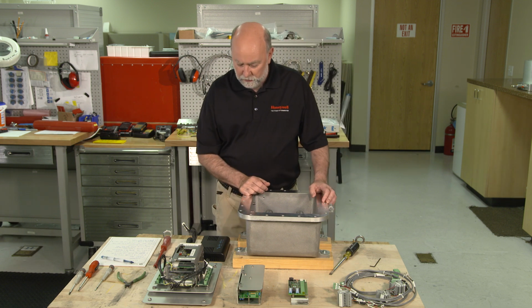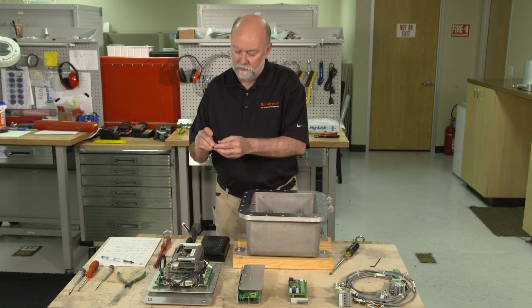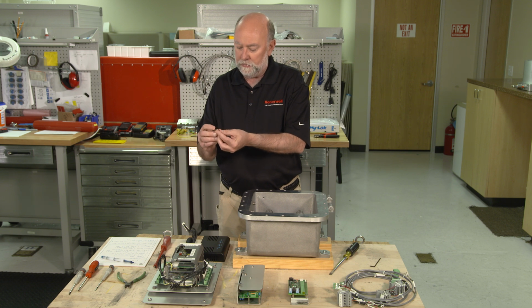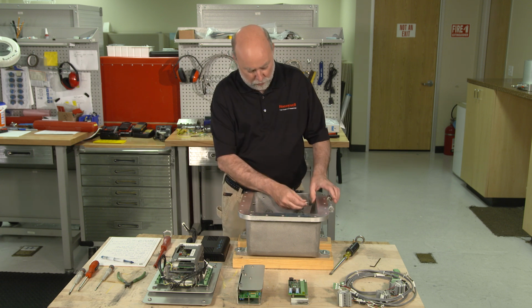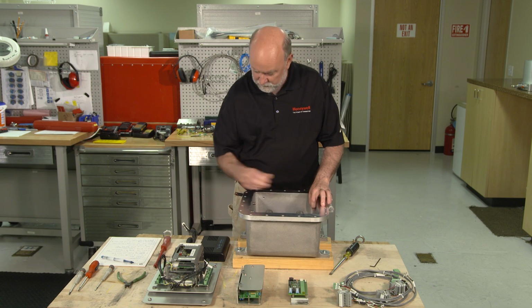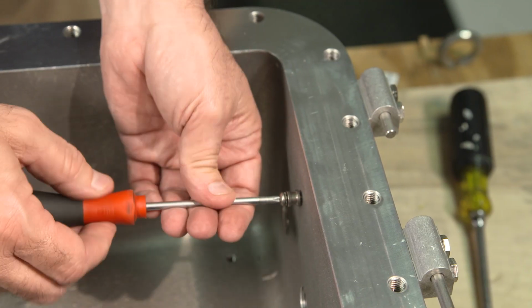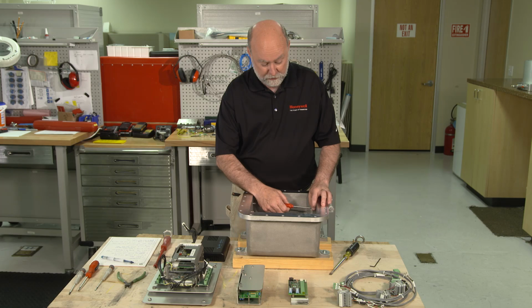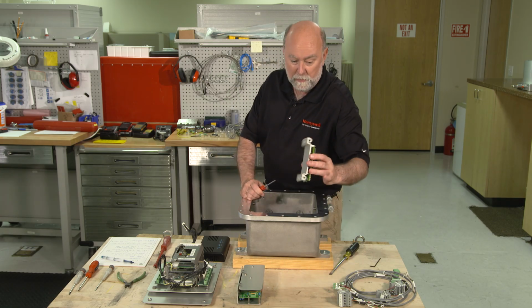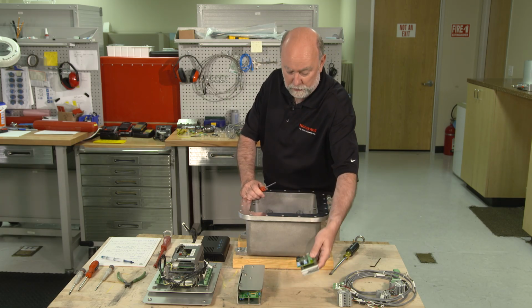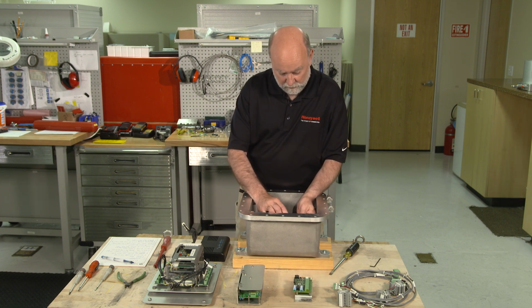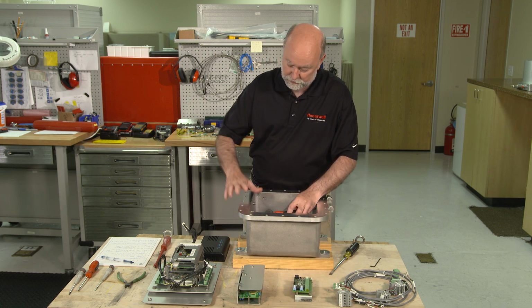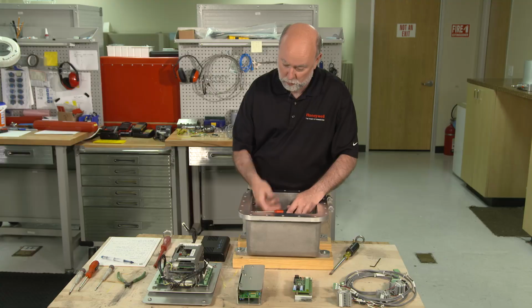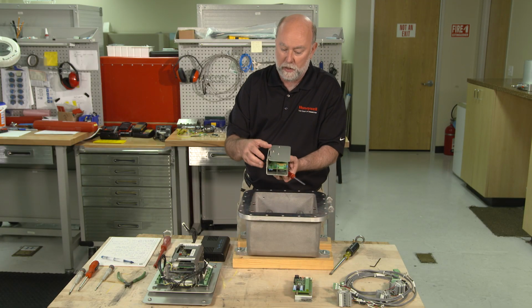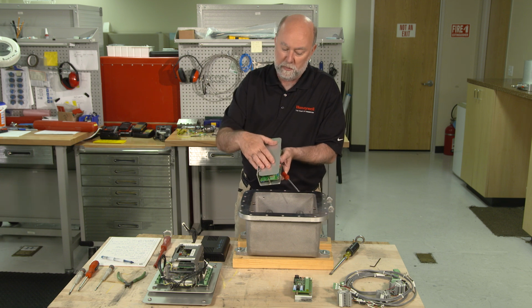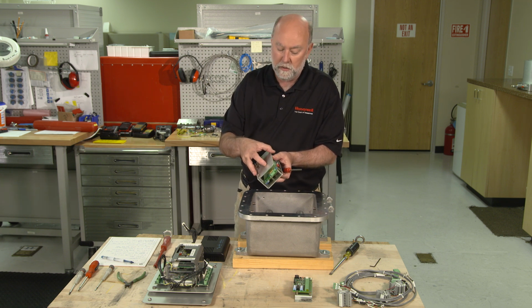Okay. So the first thing I'm going to do is identify my barrel or ferrule type studs and screws that I'm going to install in the side walls of the box here. There's 4 of these. So there are 2 on the left-hand side that are going to support the frequency controller card, which is already mounted on a bracket here with these special clips riveted to it. And I have 2 others on the right-hand side of the box over here, which are going to support the field terminal board, which is mounted already on a bracket with those same type of clips. There's a cover plate on here, which we'll have to remove when we want to wire the field terminal board up.